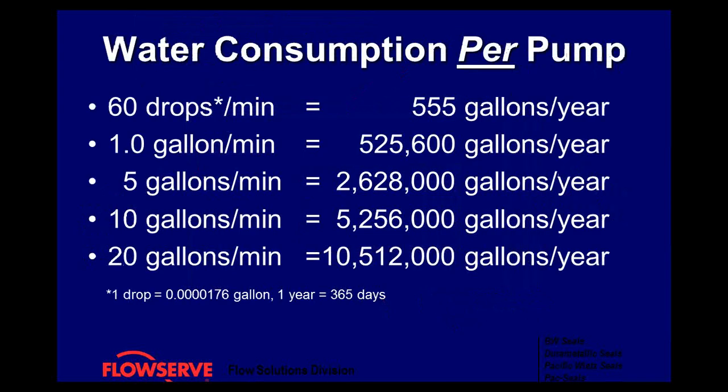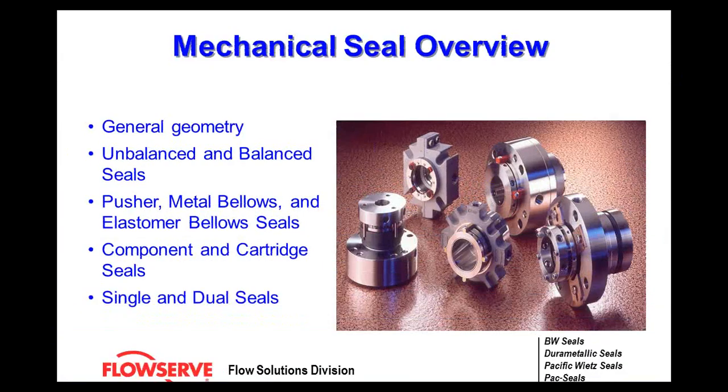Water consumption is something not always fully understood when using a packed system. One gallon per minute equals 525,600 gallons per year. If you have any packed systems at your plant, go out and find how much water in gallons per minute you're actually using, then check with accounts payable to see how much you're spending per year on city water. Packing may be inexpensive, but in the long run a mechanical seal might be the better option.